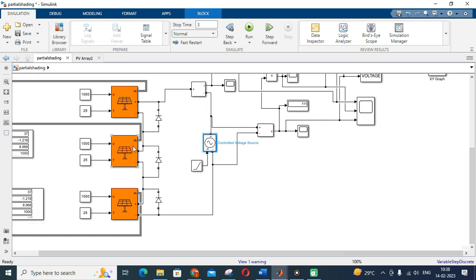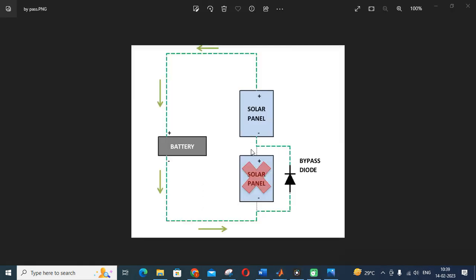A bypass diode is connected in parallel with every panel. The need for connecting this bypass diode is that if any solar panel is short-circuited, a fault occurs, or physical factors affect one panel, the other solar panels connected in series will also get affected. To avoid this condition, we use a bypass diode to maintain the operation of the remaining panels. By connecting this bypass diode, power generation continues without interruption from the affected panel.